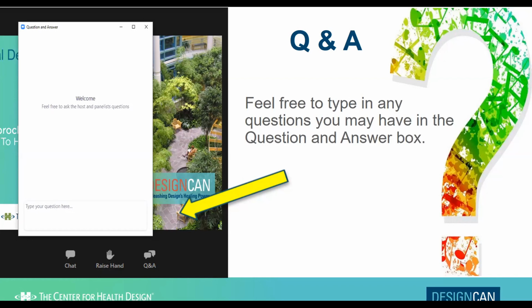That's excellent. Our next question is, how does the energy savings get reflected in the business case? What is the payback period using the setbacks? And are you able to estimate avoidable costs that might be associated with hospital acquired infections? Yes, so the energy model savings we had was a payback within less than 1 year. And we looked at the infrastructure costs that included cooling, heating, humidification, dehumidification, as well as fan energy and the use of outside air.